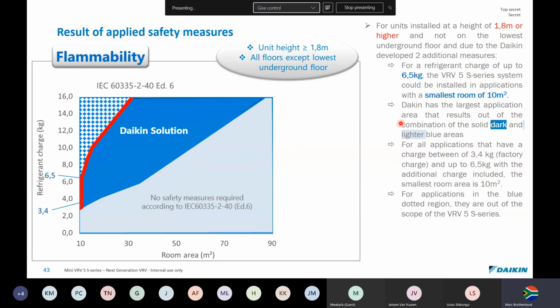So Daikin is the largest application area that results out of the combination of the solid dark and lighter blue area. So all the designs that have been done around the world, a lot of our equipment falls within the dark blue as well as the lighter blue. So for all applications that have a charge between 3.4 kilos from the factory and up to 6.5 kilograms, so if you add in another 3 kilos, the smallest room area, as I've mentioned, can be 10 square meters. For applications in the blue dotted region, they are out of scope.